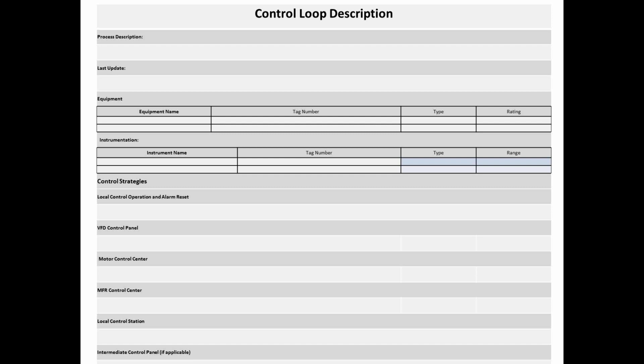Okay, I talked about the control station already. That's in error there. That local control operation alarm reset basically is a description of how the operation would be. Then when you talk about the local control station, you would talk about how you control at the local control station. We talked about local control panels. In this document, it's referred to as an intermediate control panel. If it's applicable, you would go ahead and talk about how you would control the equipment from the local control panel. And that's the first part of the local controls description.